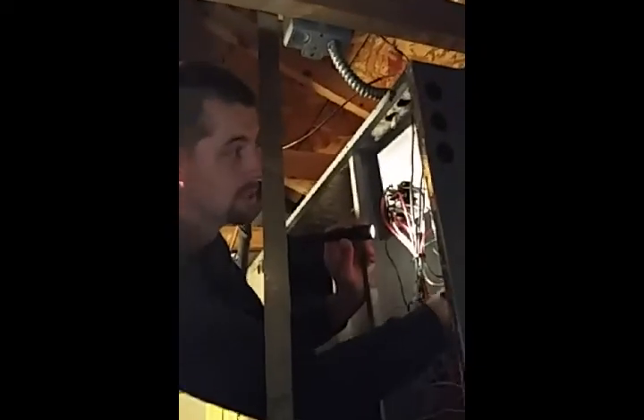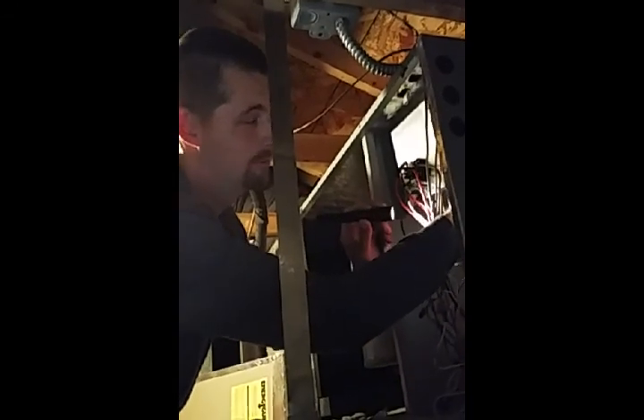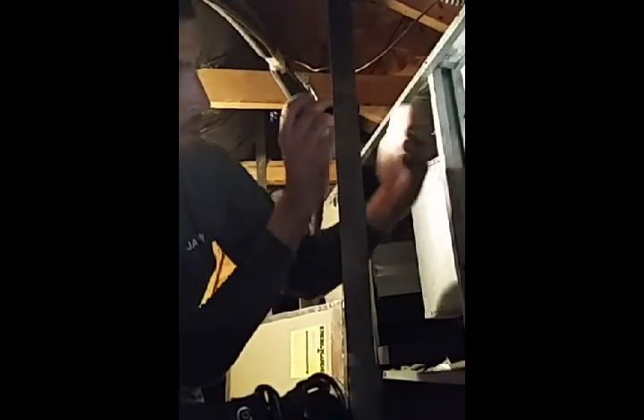So overall, everything looks very well. The heat sequencer looks to be in good condition. The heat strips themselves look to be in okay condition. And again, we're not going to get too into detail. This is a summer startup evaluation. It's not a winter startup. If this was a winter startup evaluation, I would pull out the heat strips and check resistances and make sure that my heat strips are sound.